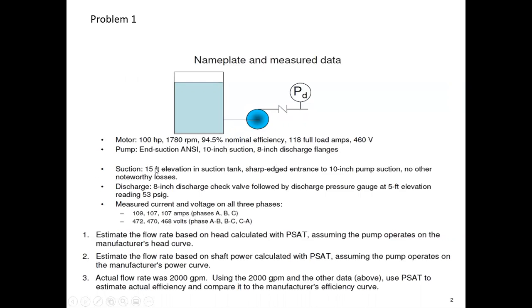Okay, on the suction side, the elevation of fluid in the tank is 15 feet. Goodness gracious. I mentioned the sharp-edged orifice entrance to the 10-inch pump suction pipe. No other noteworthy losses on the suction side. On the discharge side, we have an 8-inch discharge check valve, followed by the discharge pressure gauge at an elevation of 5 feet, reading 53 psig.